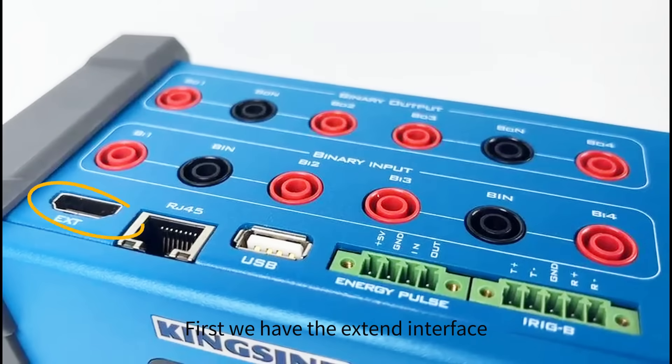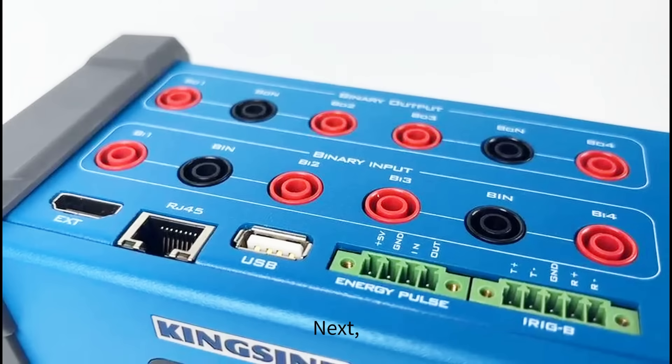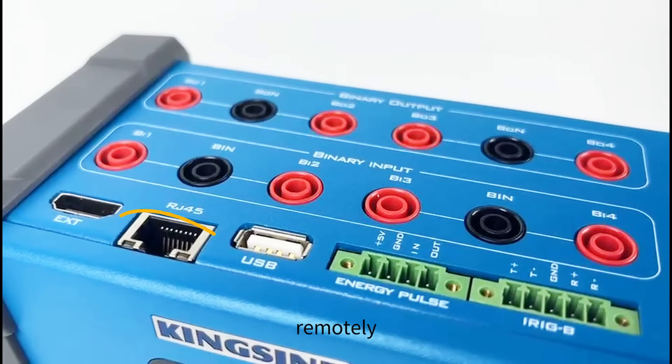First, we have the extend interface, which is used for hardware function extensions. This includes expanding the number of binary inputs/outputs, external measurements, and testing LPVT and LPCT. Next, there's the RJ45 interface, which allows for PC control, making it easy to manage and operate the device remotely.